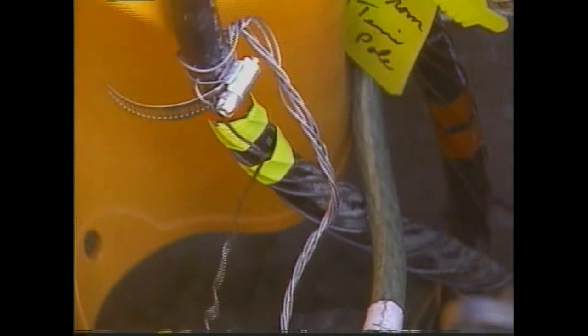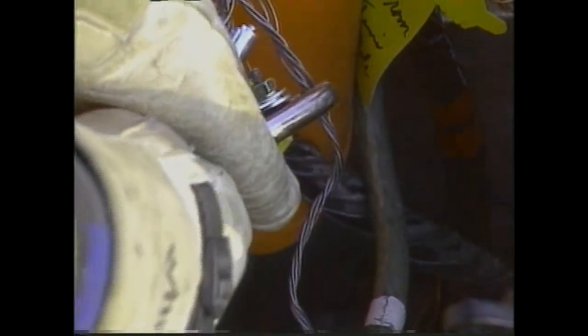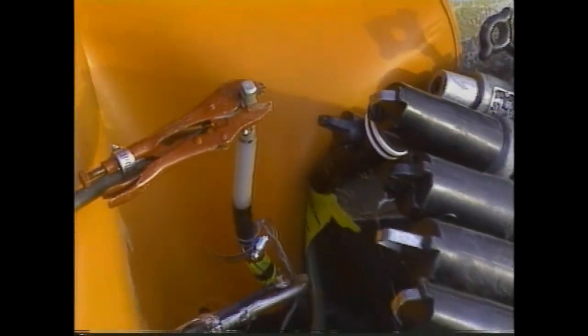I do not see a lot of people covering up this connection, but it is a good idea and should be done. Next comes the high-voltage return lead. It is connected to the neutral of the cable that we will be thumping. After the neutral connection has been made, we can connect up the thumper's high-voltage output connection to the faulted conductor.